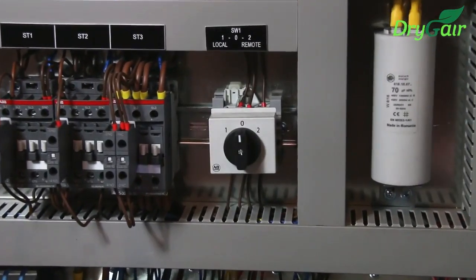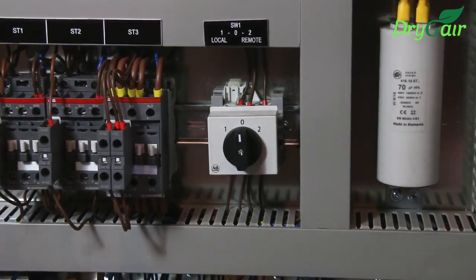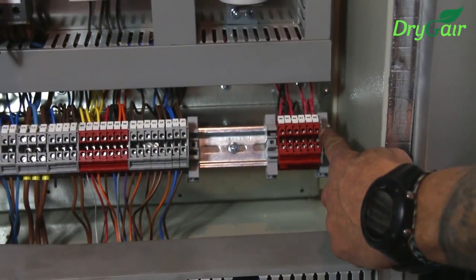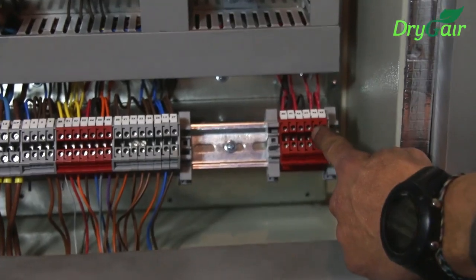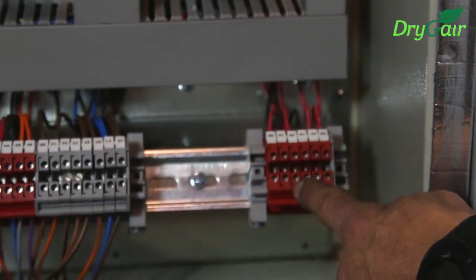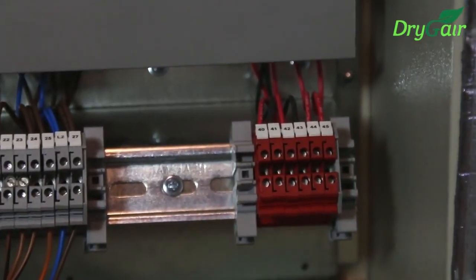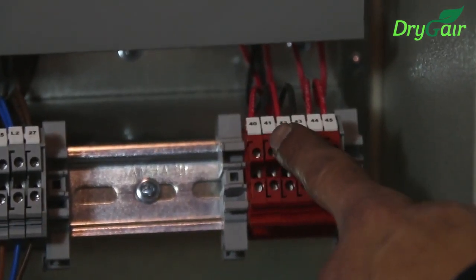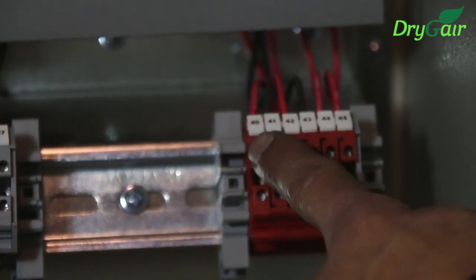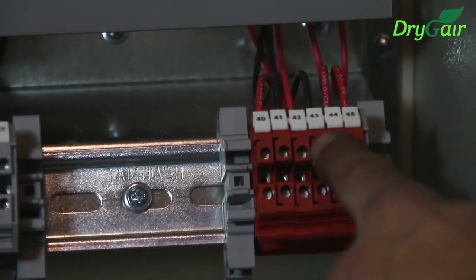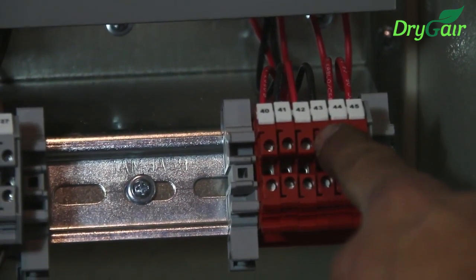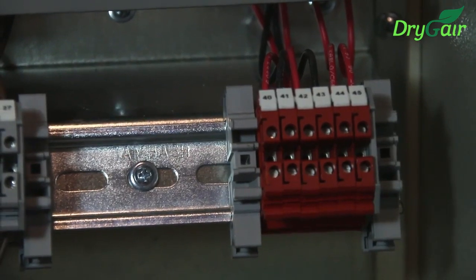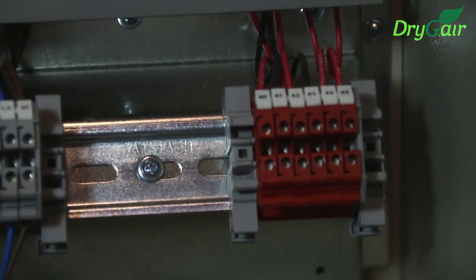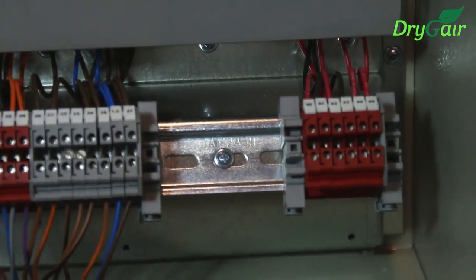If you choose to work using the remote operating mode too, you will need to connect your climate control system to the unit. You can do this by connecting 24-volt AC cables to the relays shown here. Connection to numbers 40 and 41 will allow the system to remotely start and stop. Connection to numbers 42 and 43 will allow the system to send a remote drying command. Call your climate control expert for assistance in setting up the connection.